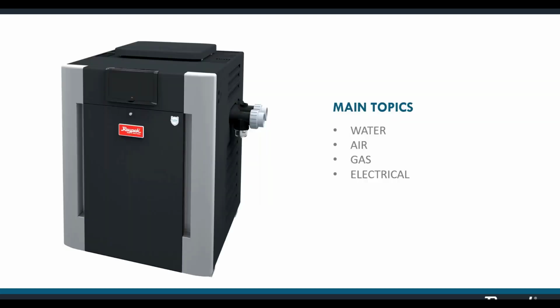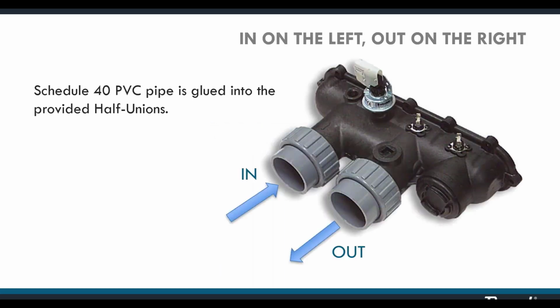We're going to break the installation down by topic here. So we'll go with water, air, gas, and electrical. I'm going to start with water because that's why we're here. We're in a water industry. After positioning the heater in its permanent location, you'll plumb the incoming water line from the filter to the left side port. There's an arrow at the top of the inlet, so you don't forget. Don't plumb it backwards. In on the left, out on the right.